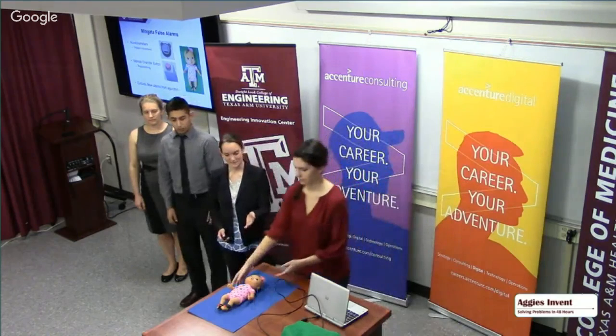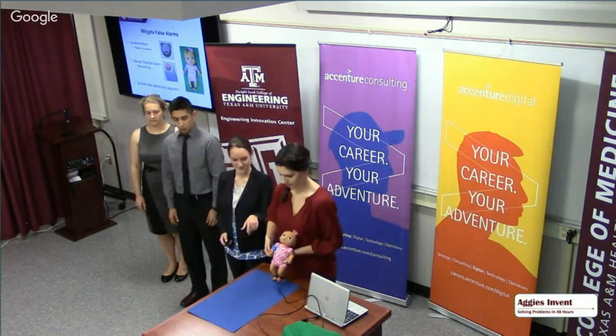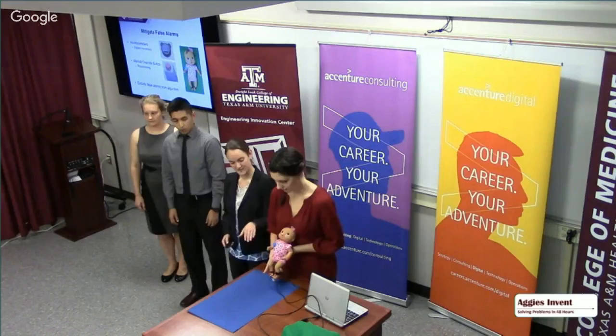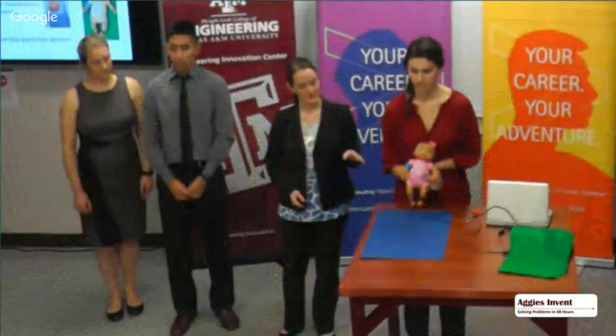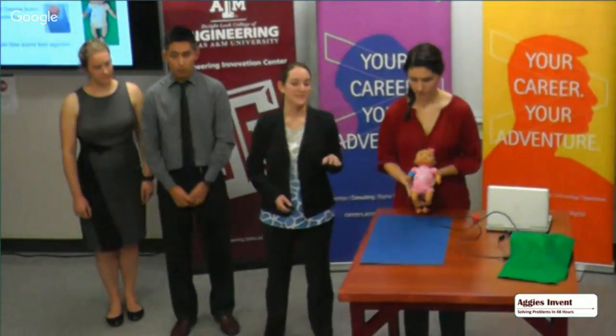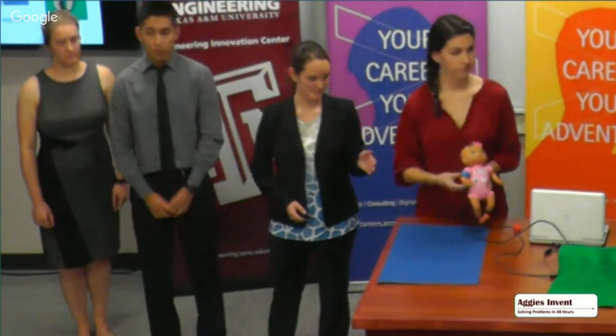As you can see on this baby doll, we have the accelerometers attached to all 4 limbs, so that'll detect when the child's moving. As long as the child is moving, the alarms will be silenced, because we know that the alarm would only be going off simply because of the movement.